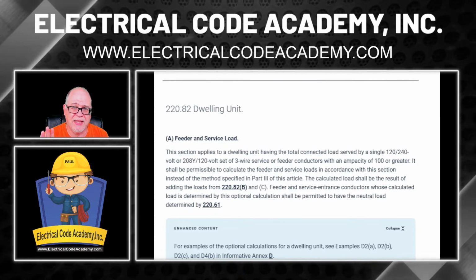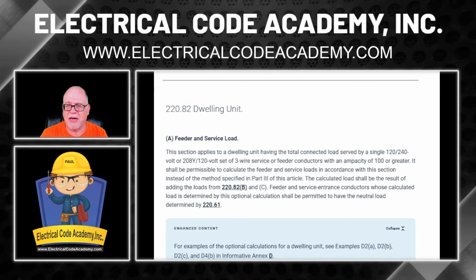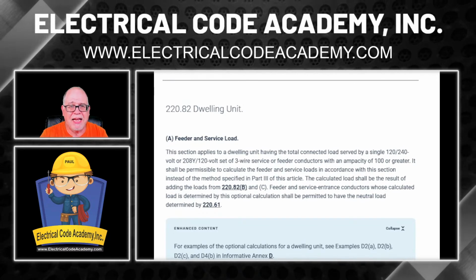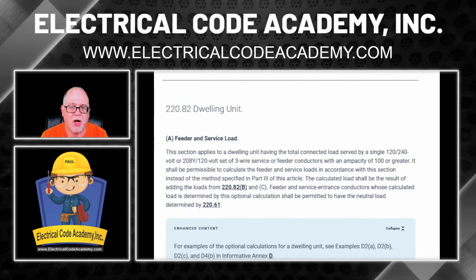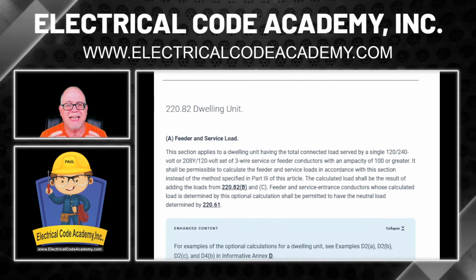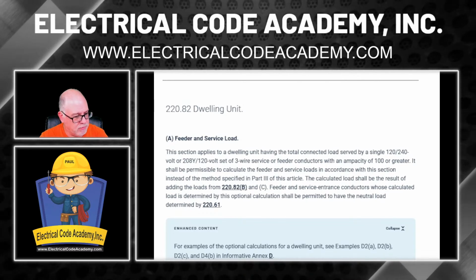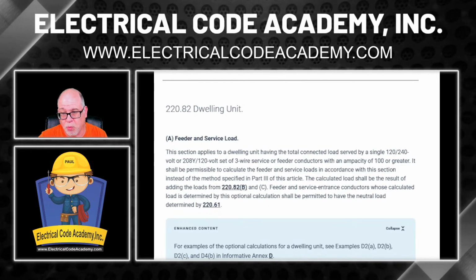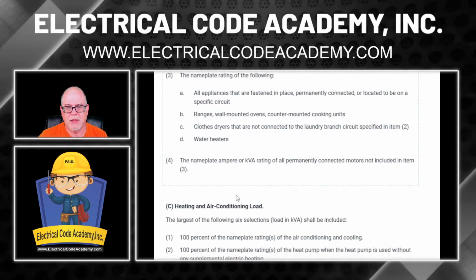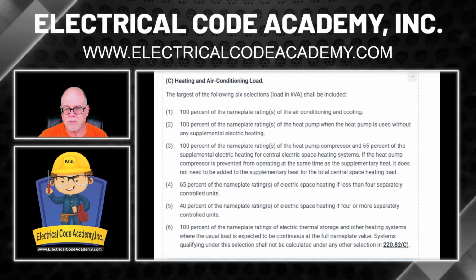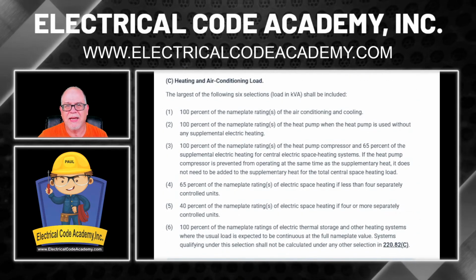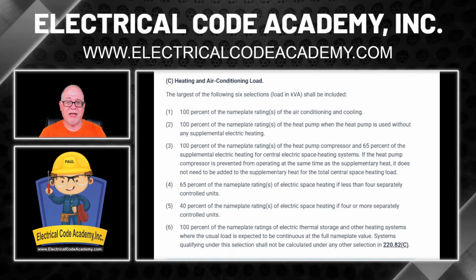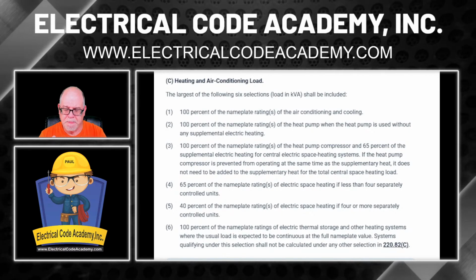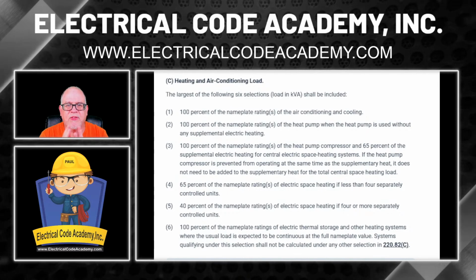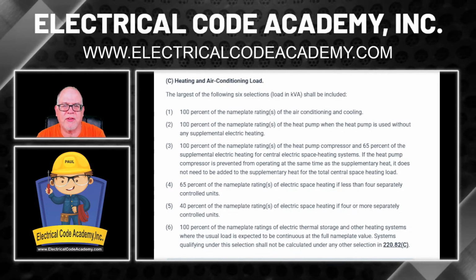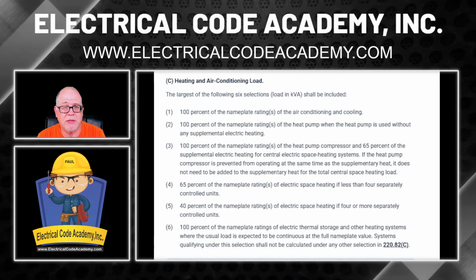We're not even doing any of that because we're not even looking at cooking. We're not even looking at appliances. We're not even looking at 3 VA per square foot. All we're being asked to do is deal with the heating and air conditioning, right? So we want to move on down to what we're working with in our question, and that is right here. So here we've got the heating and air conditioning, and it's broken down into 6 pieces here, okay? Now, it says the largest of the following 6 selections shall be included.